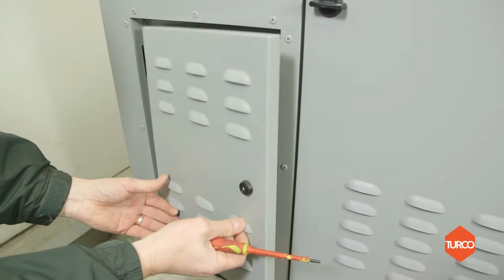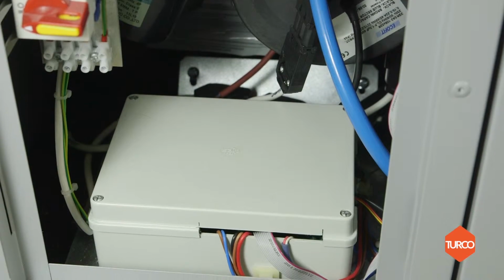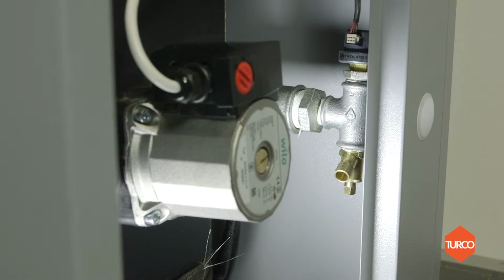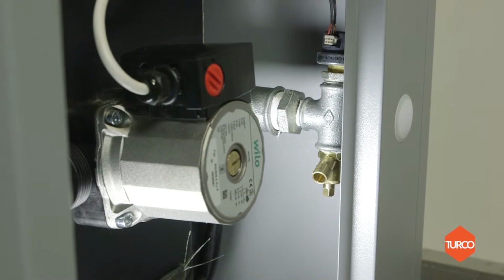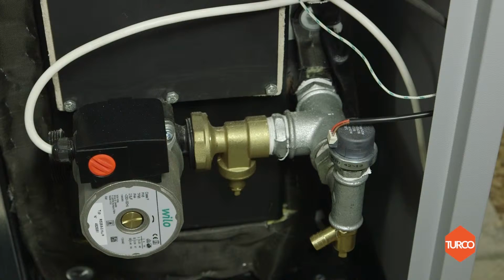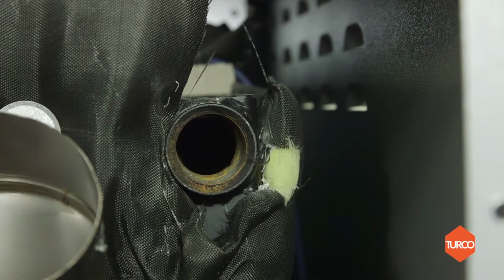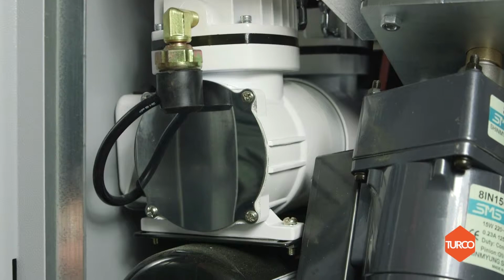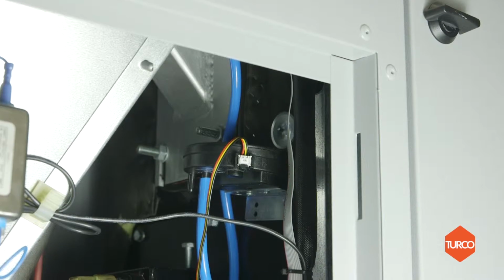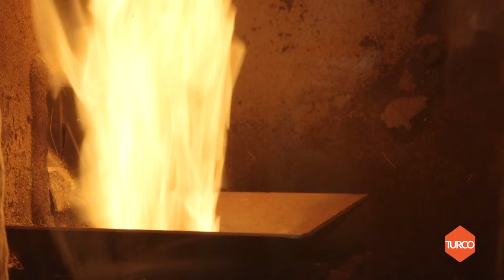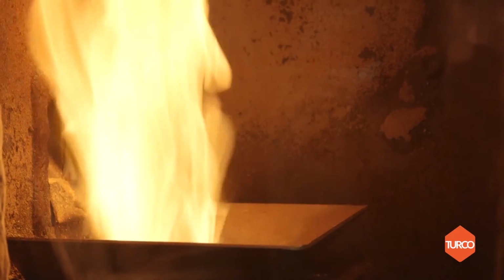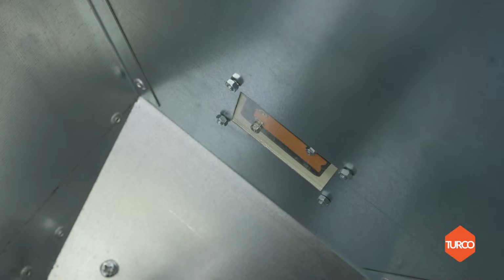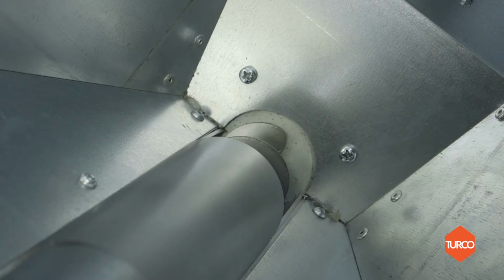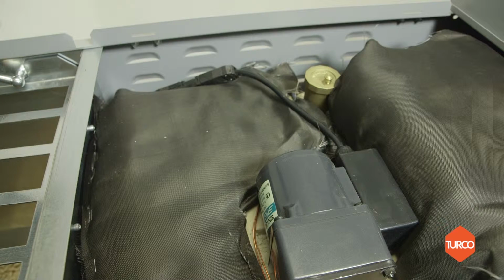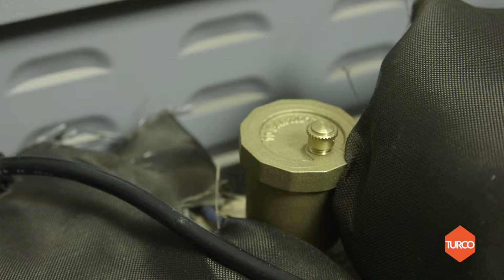Behind easily removable panels are the control board enclosure, water pressure sensor, circulating pump, flow and return connections, compressor and tank for automatic burner cleaning, vacuum regulator which assists with maintaining negative pressure in the combustion chamber. Within the hopper you will find the low-level pellet sensor and the auger flight. On opening the lid over the boiler, one will find the boiler cleaning motor and the automatic air vent.